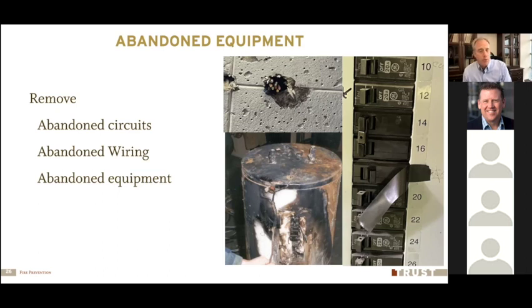It's not there anymore. The person who put that tape on there was trying to protect people, because there's something dangerous on the other end of that circuit or in that circuit that we don't want people to come into contact with if the breaker is on. But it's amazing how often the person who did this doesn't work here anymore, and people don't know why that breaker is taped off. So if you've got abandoned equipment or something that's dangerous electrically on a circuit, lock out, tag out that circuit, or remove that abandoned circuit.